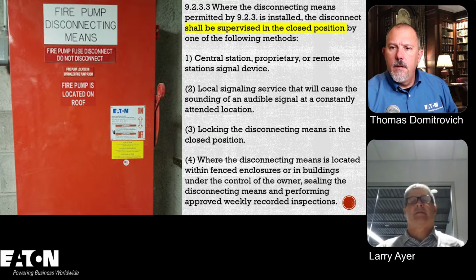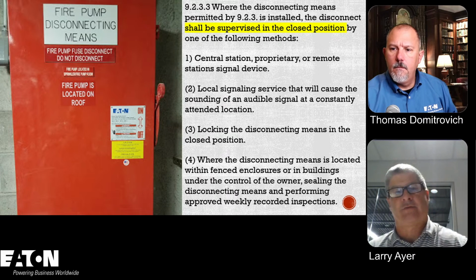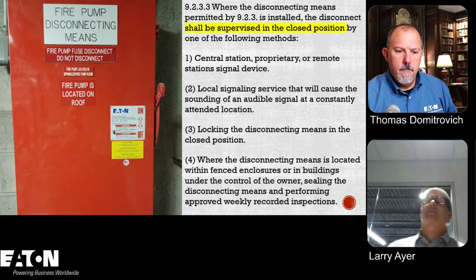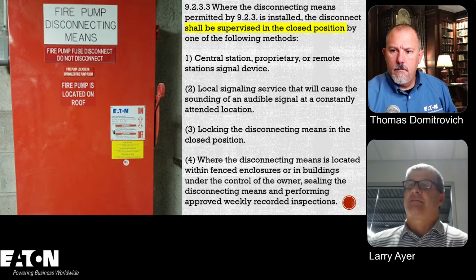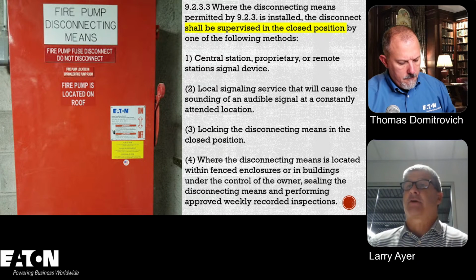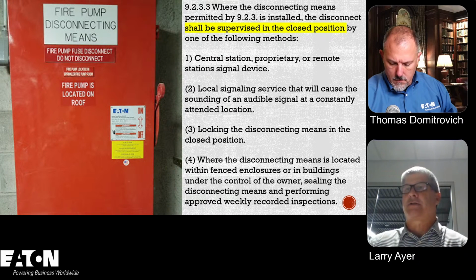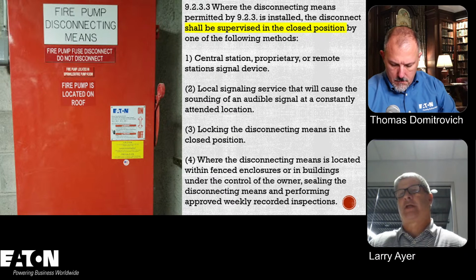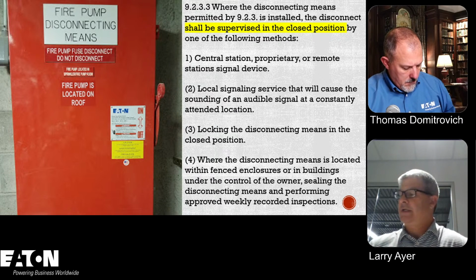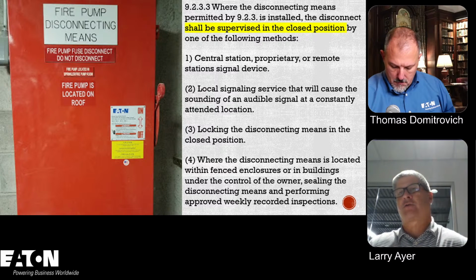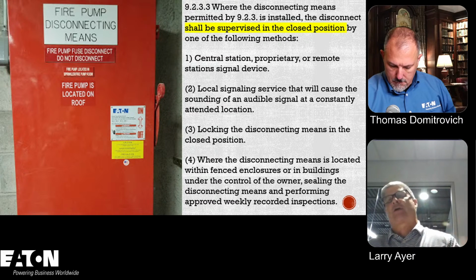Well, one of the things is I think it's a question, where do you apply coordination on one level? I would assume that means that if you have a fire pump controller and a fire pump disconnect tapped off the service, I do think the code is silent there on the coordination. So once you tap off the service, you're going to put a service disconnect, you're going to put a fuse or a breaker, then you're going to go to the fire pump listed controller, and that is going to have its own overcurrent protection, but it's really kind of silent on how that coordinates.